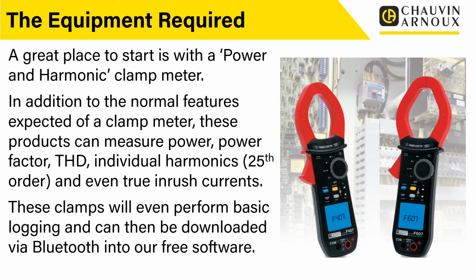And when you've got a current and a voltage connection, then obviously the meter can measure power. And that's the difference between these and a normal meter. You've got the current and the voltage at the same time, which then gives you these power measurements. And obviously, having a clamp meter that can very quickly do power factor, can very quickly measure total harmonic distortion, so tell you whether you've got a harmonics issue.